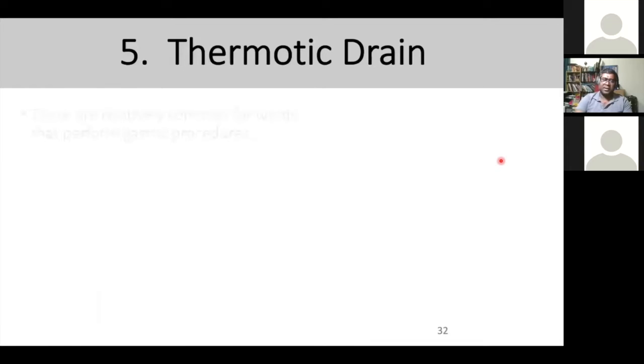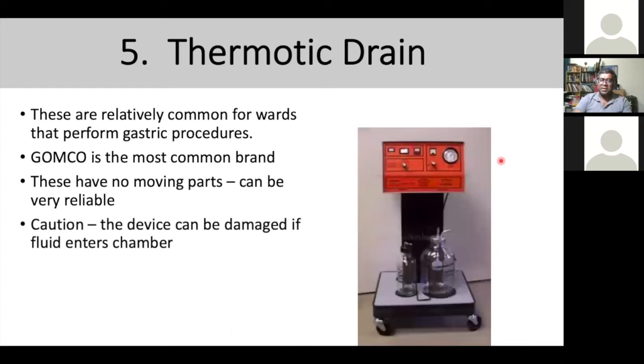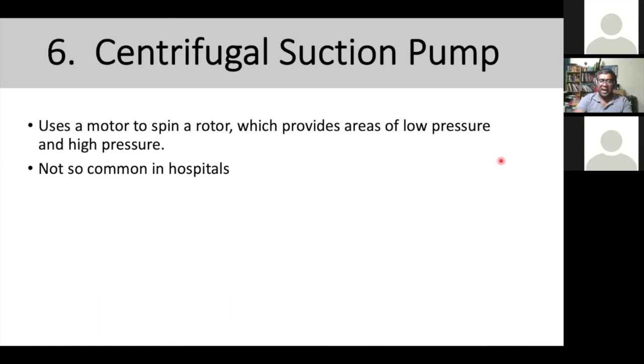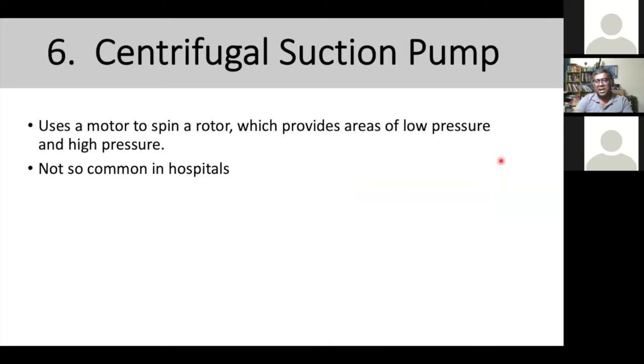Number five is the thermotic drain, commonly seen in certain departments — not all hospitals — but in departments that perform gastric procedures. Using heat and no moving parts, it creates pressure in the chamber itself. It very rarely breaks down; the only problem you'll see is damage if fluid enters the chamber.